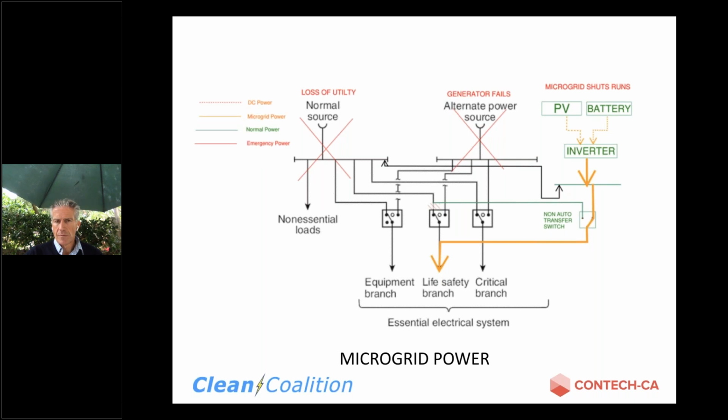Wonderful. And Craig is asking, what percentage of the normal loads are the critical loads? Oh gosh, I think Richmond is around 40%. Kaiser Richmond, and then Jeff, do you have the San Benito? No, I don't know at San Benito, but I would agree with you at Kaiser. The reason we know is that the first Tuesday of every month, they do their generator testing, and the hospital, as I said, ran around 750 to 800 kW and would drop to 300 or 400 kW, which would be just covering the critical loads. So maybe it's closer to 50%, but 40 or 50%.